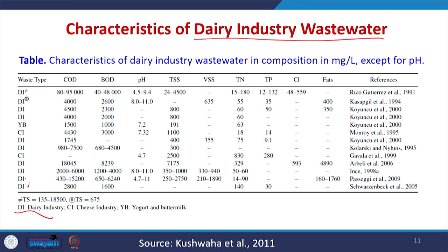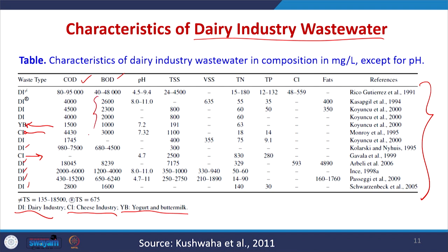Dairy industry wastewater characteristics differ by product type: DI stands for dairy industry in general, CI for cheese processing industry, and YB for yogurt and buttermilk. These characteristics from the literature show that the BOD range is very high, varying from 40 to 48,000. Representative values include 2600, 2300, 2000, and 1000, with BOD beyond 1000 in virtually all cases. pH, TSS, VSS, total nitrogen, and total phosphorus are all important parameters, with nitrogen content and fats also present.